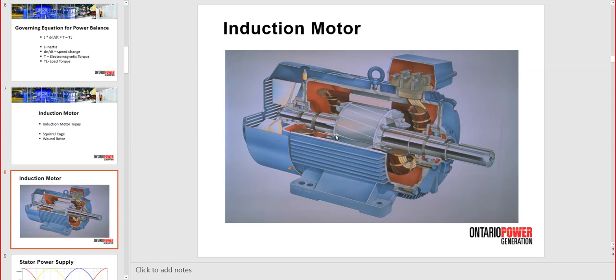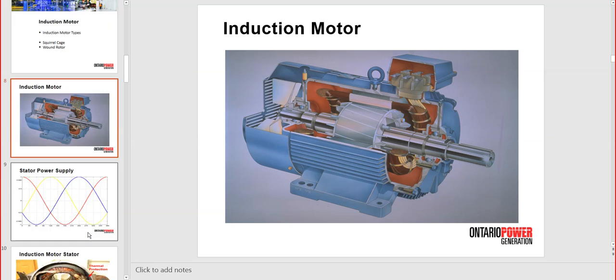Okay, so any questions regarding the motor? That was very much in a nutshell, very rapidly going through the parameters and explaining what is inside. You also see on the shaft here on the cage some wings. Those are for cooling purposes, and then the little cylindrical holes sometimes in the ring are for dynamic balance. So in order to achieve a perfect dynamic balance, these little things are shaved off as required. As we said, the air gap in these motors is no more than 0.5 millimeter.